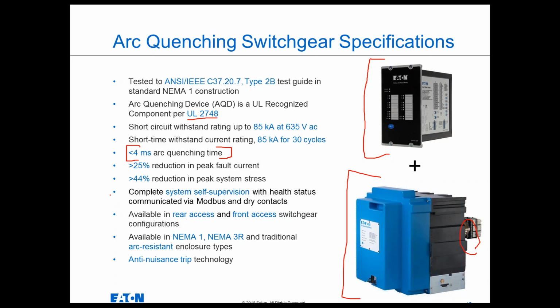It's available in all enclosure types, so traditional indoor, NEMA 1, NEMA 3R outdoor, so it essentially creates the world's first outdoor arc resistant switchgear, because up until this point, NEMA 3R gear has not been tested to the arc resistant test guide. And it's even available in an arc resistant enclosure. If you were interested in sort of a belt and suspenders approach to arc resistance, active system, passive system, some redundancy there, it's also available in that.